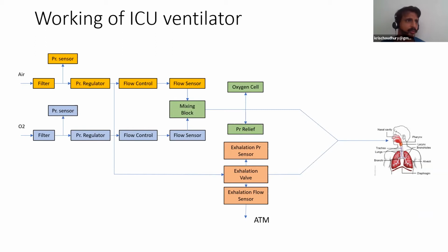Those regulators would be more expensive. After that, once you've regulated the pressure to a certain level, you need to get into flow control, where you basically control the amount of flow that is going into the patient.